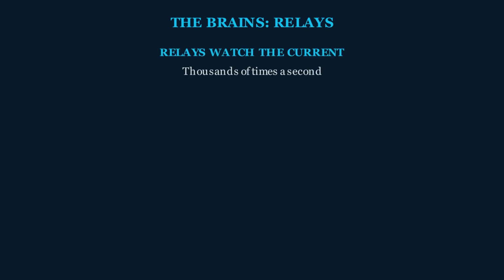A relay is a device that watches. Every line coming into the substation has sensors on it measuring the current and the voltage, continuously, thousands of times a second. In normal operation, the numbers sit in a familiar range, and the relays do nothing at all. But the instant a fault hits, the instant the current spikes to that impossible level, the relay recognizes the signature and, in milliseconds, sends the command, "Open this specific breaker now."